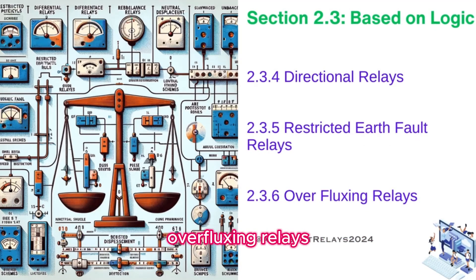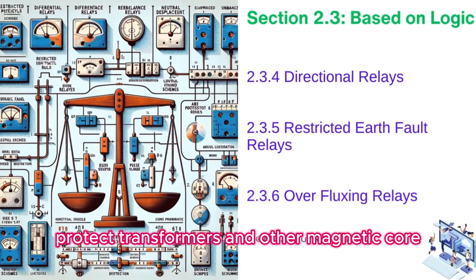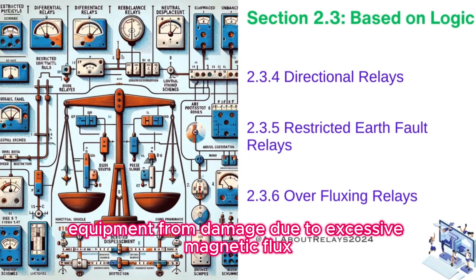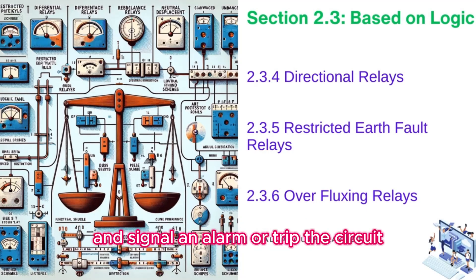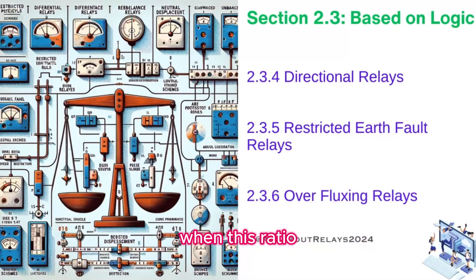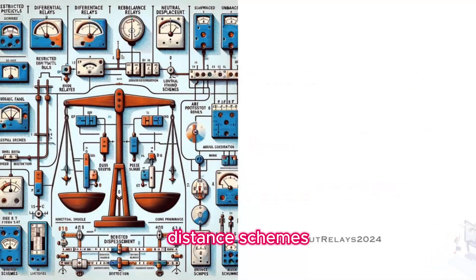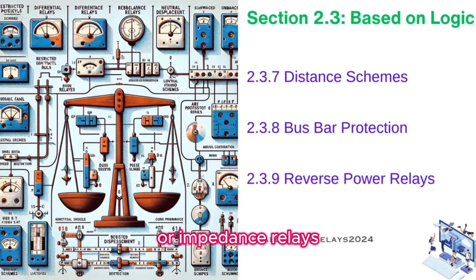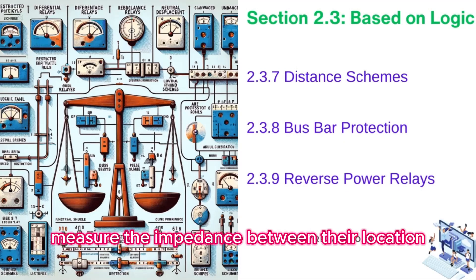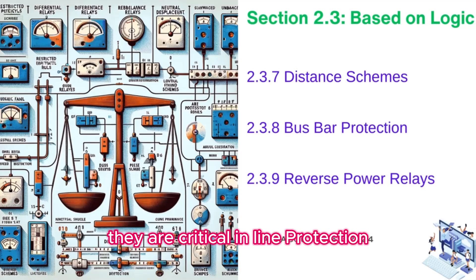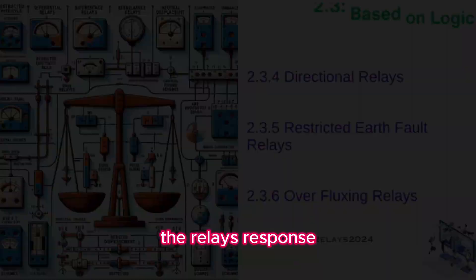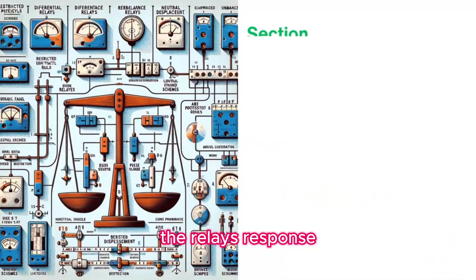Overfluxing relays protect transformers and other magnetic core equipment from damage due to excessive magnetic flux. They monitor the voltage-to-frequency ratio and signal an alarm or trip the circuit when this ratio exceeds safe limits. Distance relays, or impedance relays, measure the impedance between their location and a fault. They are critical in line protection where the fault's distance determines the relay's response.